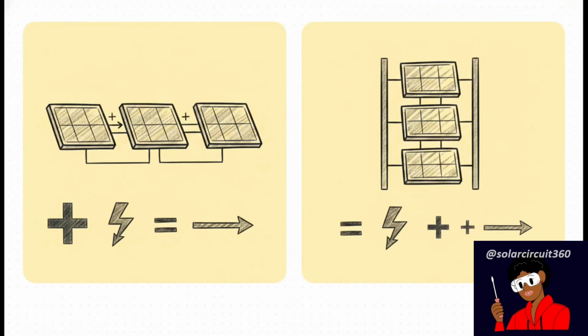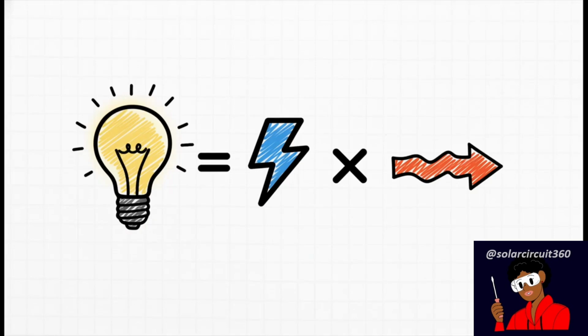Looking at the visual comparison here, we've got 2 unbreakable laws of physics side by side. When you wire your solar panels in series, their voltages add together, but the current stays exactly the same. On the flip side, if you wire those strings in parallel, the current adds together, but the voltage stays constant. Charge controllers have very strict limits for both of these, so these 2 rules literally dictate how your strings have to be sized. And really, the whole thing anchors on this one incredibly simple formula.